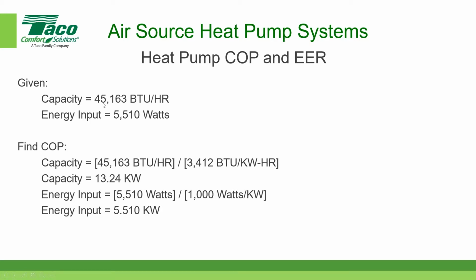So we take the capacity, which is in kW now, 13.24. We've converted the 45,163 BTUs per hour into kW, and the energy input was given to us in watts, so we simply divided that by 1,000 to come up with kW. Now the coefficient of performance is equal to the capacity divided by the energy input, which in this case is 2.40. So the coefficient of performance in this specific case is 2.40.